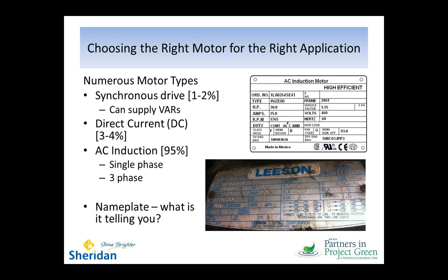So here are some of the things you're going to see on a typical nameplate. If you look at the one in the top right, you can see that next to the words service factor, there's a 1.15, and then a small indication of three-phase. You see 460 volts below that, 60 hertz. So it's told you that this is the electrical service it's expecting, and it wants to be close to that. It's also going to tell you on the mechanical side the rated horsepower, in this case 30, and then it's indicating amps and RPM, and these are the rated amperes and RPM. So this is its nominal operating range. It wants to be pushing 30 horsepower. It will be drawing 35 amps, and it would want to spin at 1765.